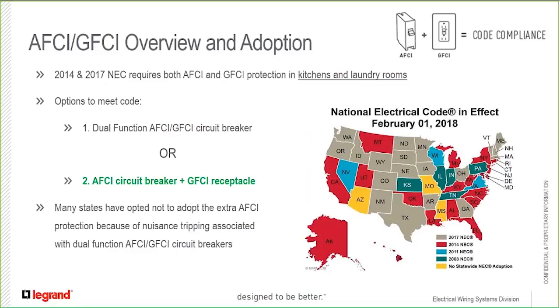You'll see at the right here the code adoption map throughout America, and basically a lot of states have adopted the 2017 code and a lot have adopted the 2014 code. And you'll see in blue and green there states that are still on older cycles of the code. Now, many states have opted not to adopt the extra AFCI protection required in kitchens and laundry rooms because of nuisance tripping associated with dual function AFCI GFCI circuit breakers. So particularly North Carolina and Oregon have chosen not to adopt this portion of the code, mainly because of the nuisance tripping associated with these dual function AFCI GFCI circuit breakers.